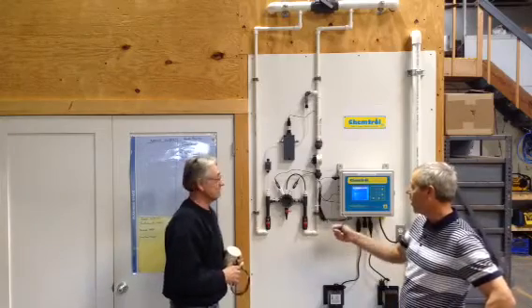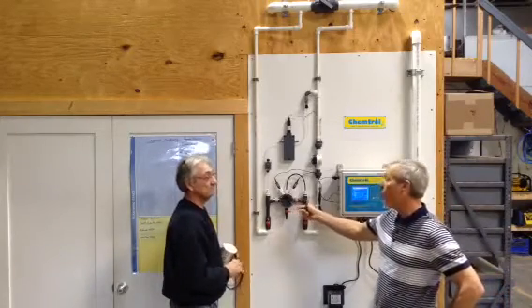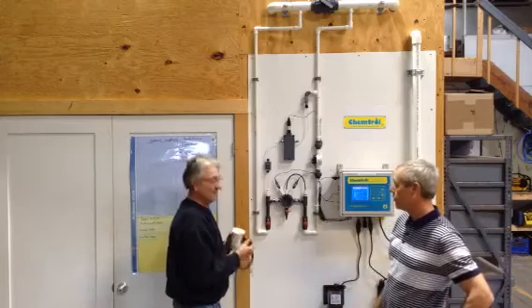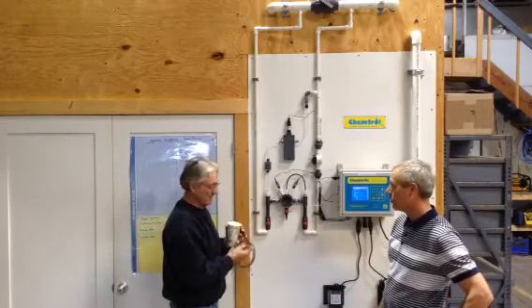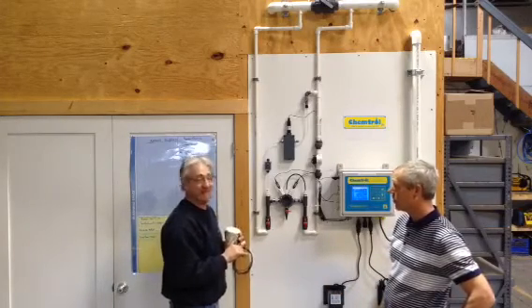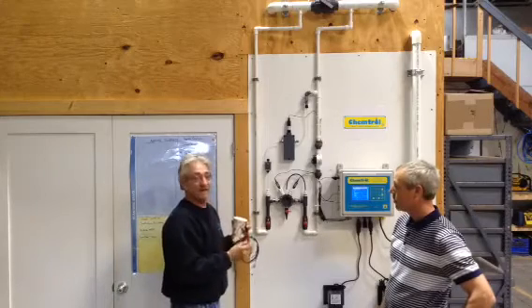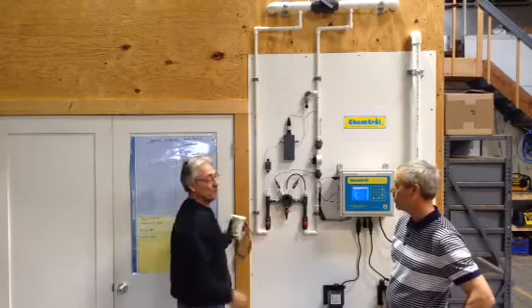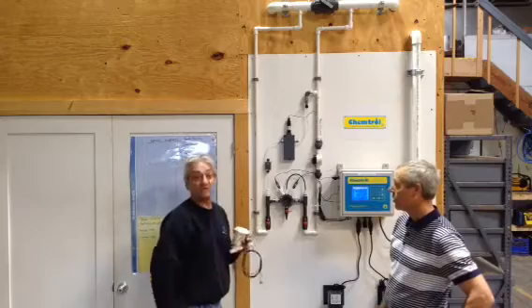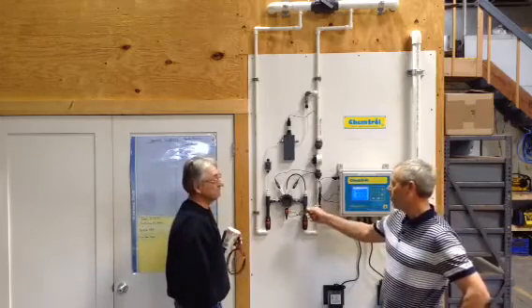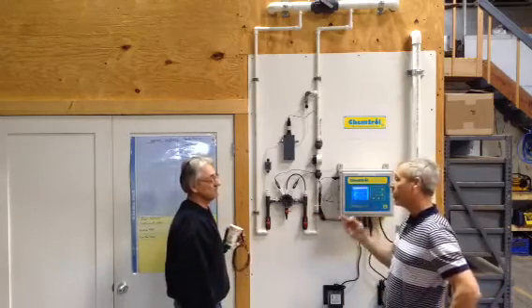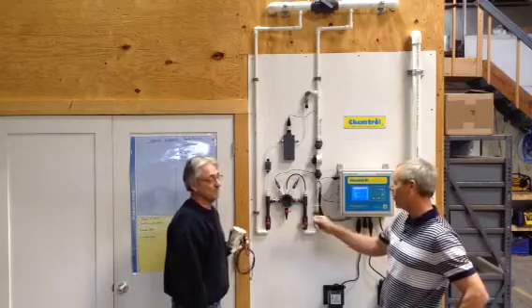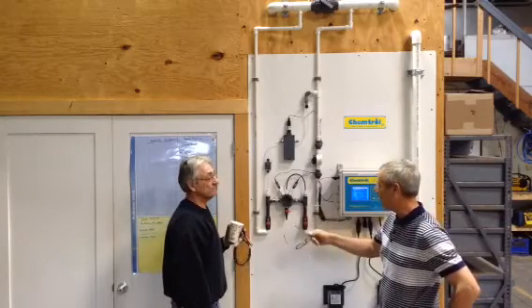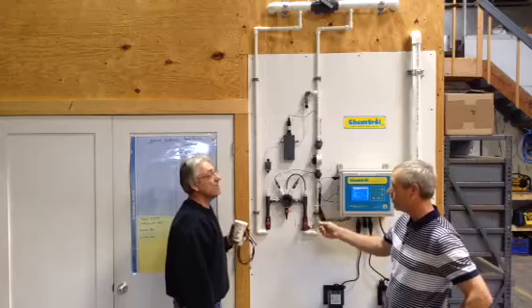And you say like 20 minutes, so 20 minutes and these should go back to normal calibration? Anything that you've put on the end, either any of the soap, anything that may have an acidic base to it, it'll finally wash off, and it's going to be back to a normal reading of the water that's coming through the cell. And if you clean it, because you're not getting proper readings on your control or your strand or whatever, and you put it back in, possibly a bad probe. Could be a bad probe.